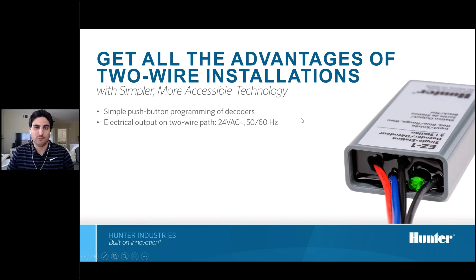We've got 24 volts, 50 to 60 hertz on the 2-wire path. Like I said, that makes it more reliable and easier to troubleshoot down the road. You can get up to two 24-volt solenoids to operate per individual EZ1 output. They're waterproof, so they're not going to get full of water in a valve box. You get upwards of a half mile or one kilometer in any direction for your 2-wire paths, and we can get 54 zones, or 28 zones with your Pro C.